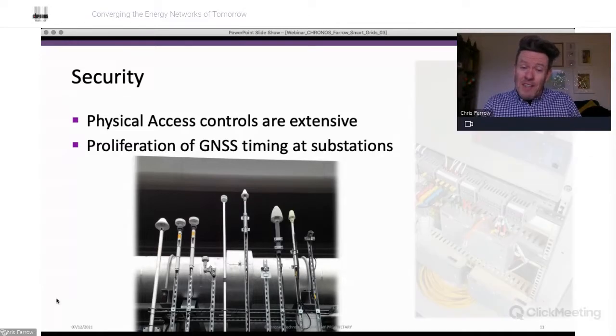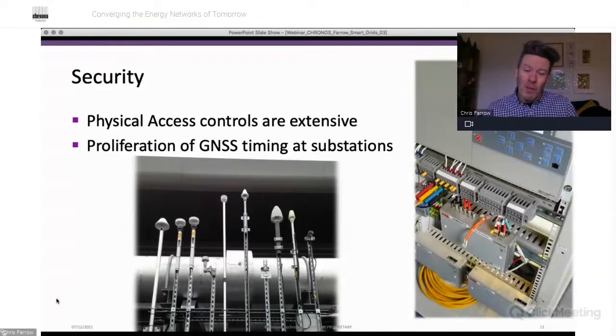Substations typically have antenna farms, with multiple racks assembled by system integrators, each typically including its own time reference, often different manufacturers or modules of GNSS receivers. So in just one substation we might end up with something like 8 or 10 separate satellite antennas. With a GNSS firewall, we can use one outside antenna with in-depth signal analysis that looks for spoofing and jamming events, and provide that signal through a splitter to all the timing receivers in those racks.